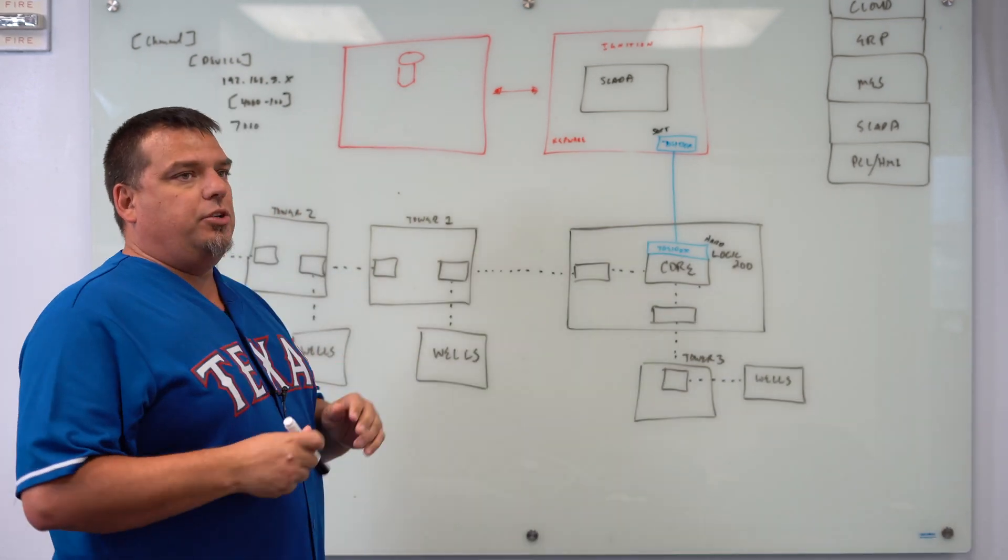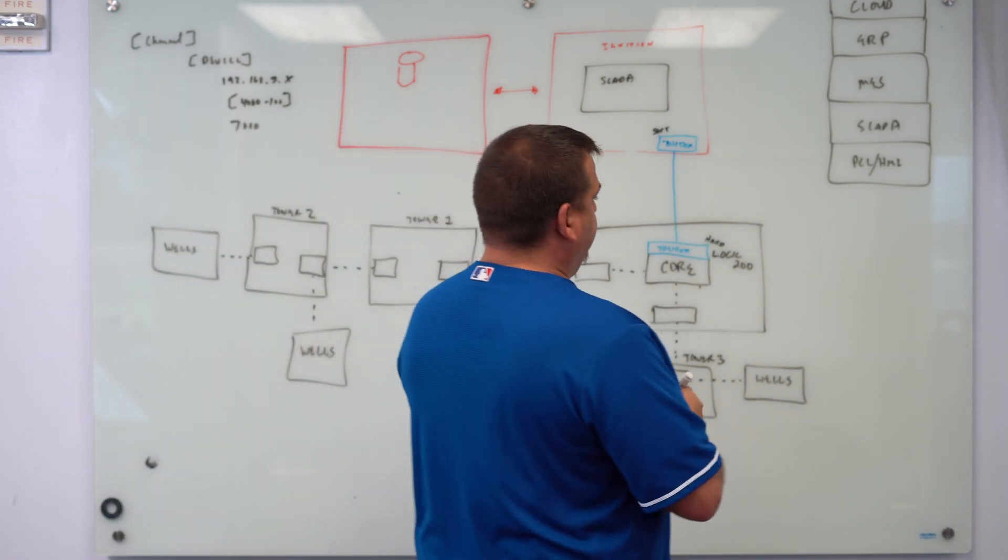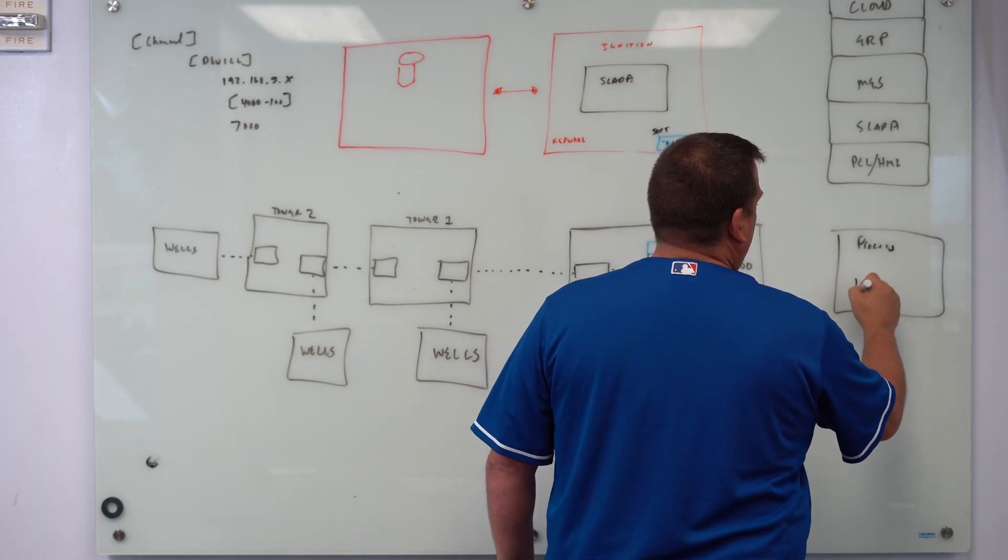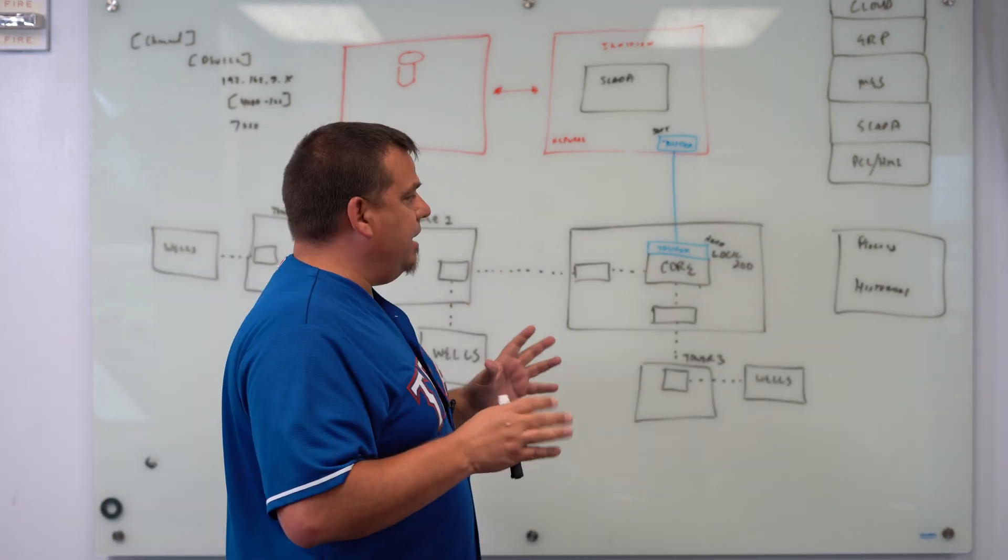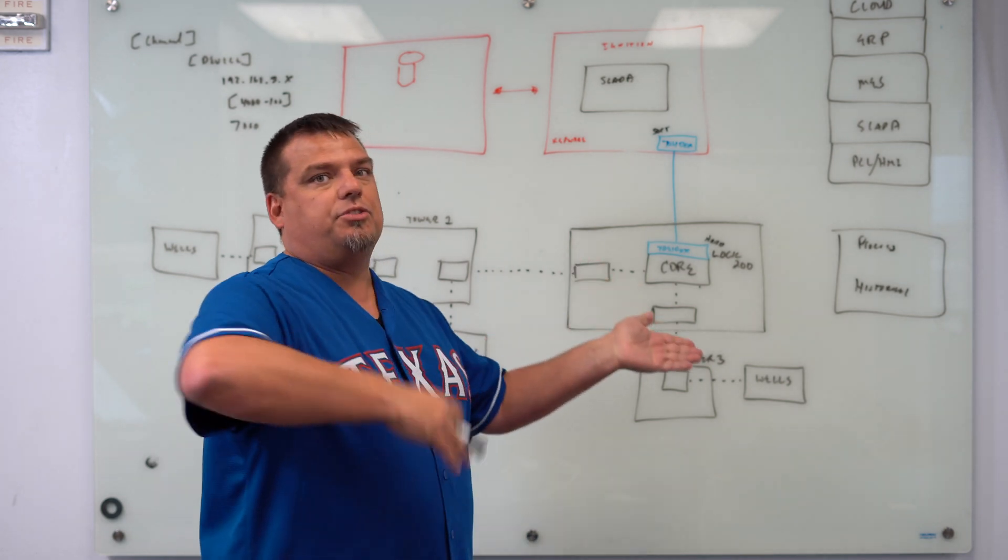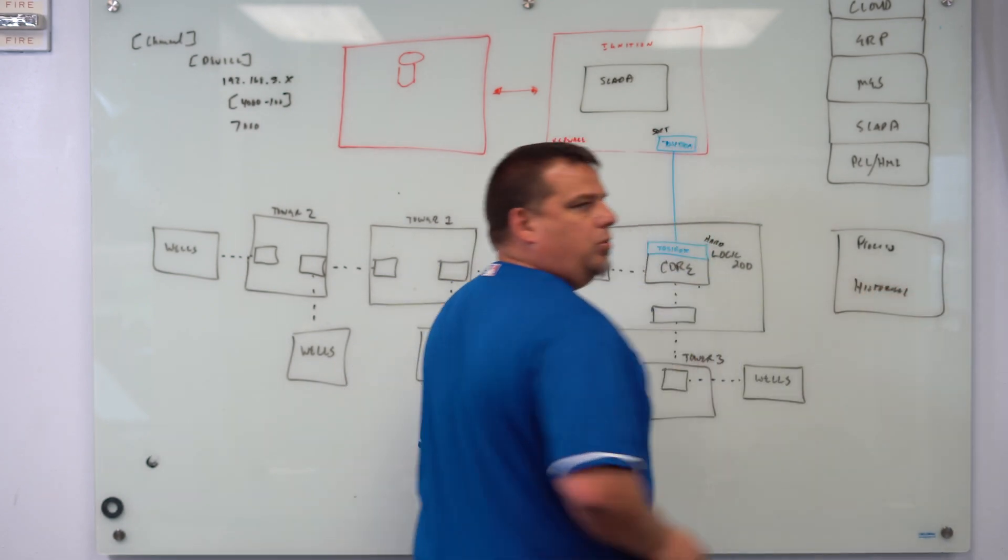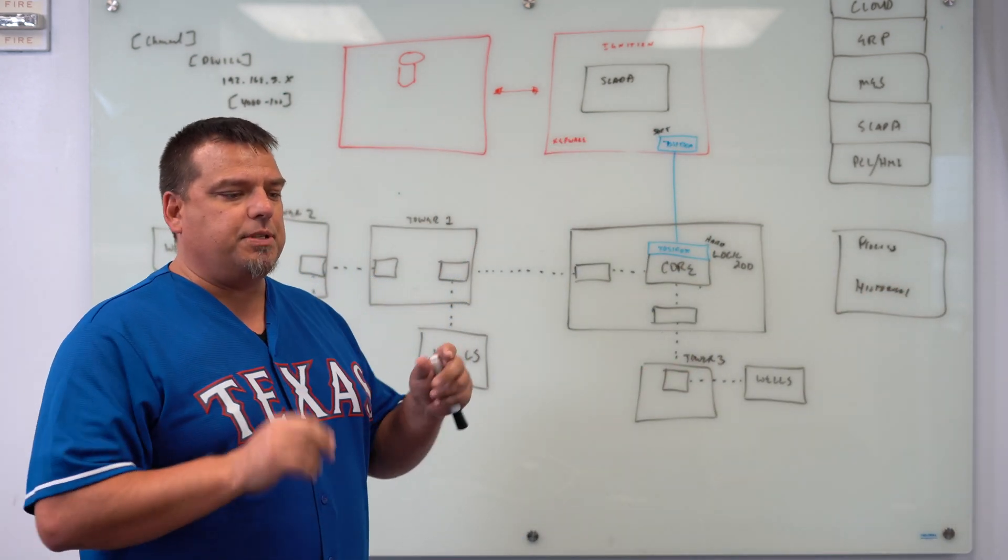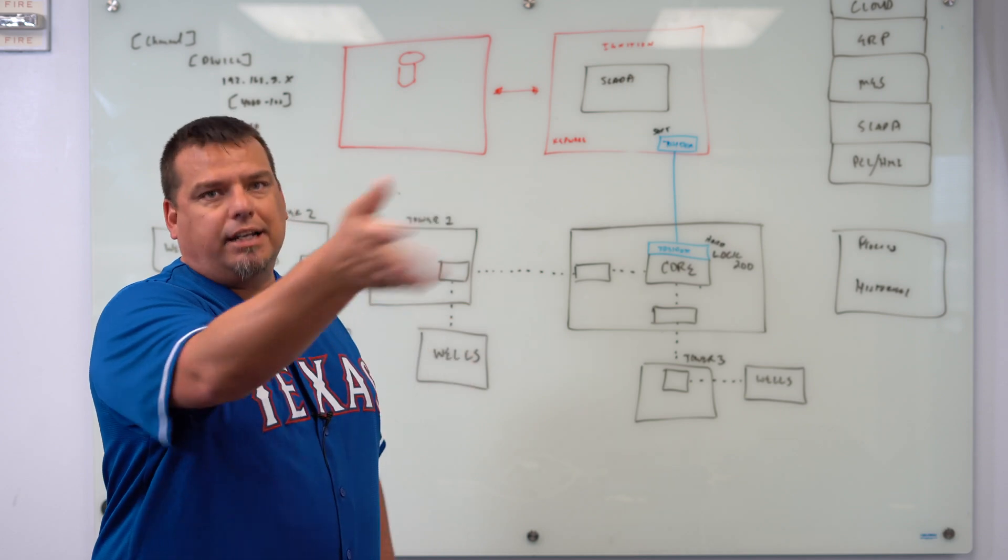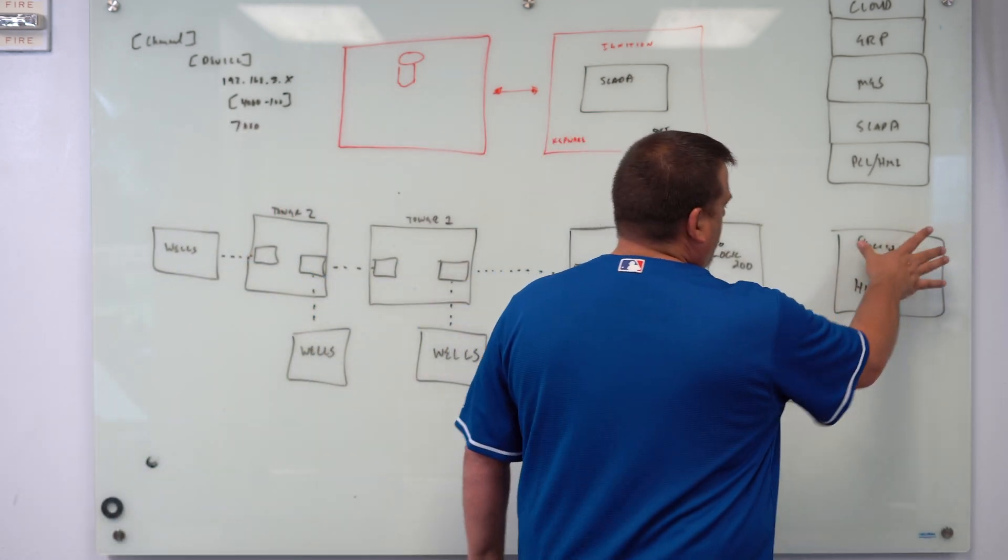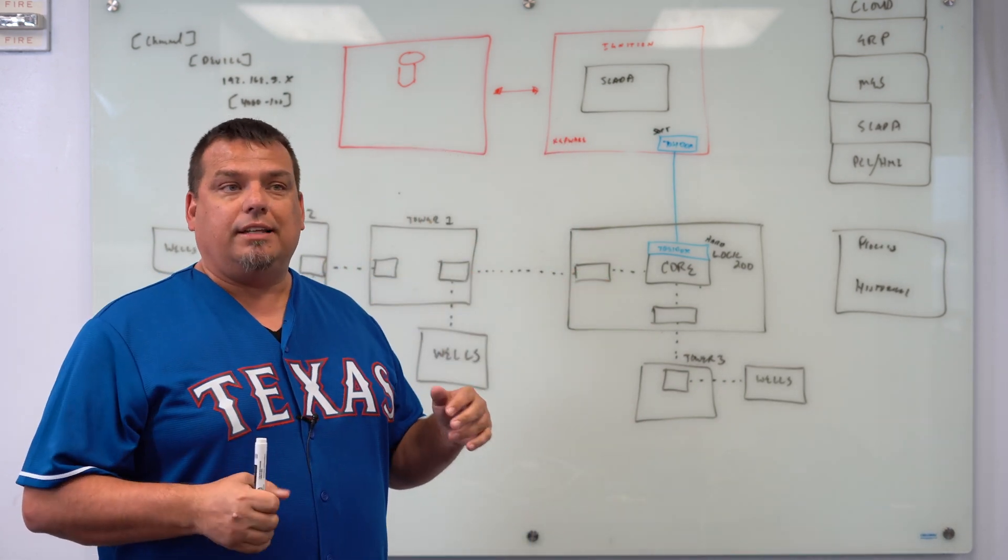We've configured Kepware to talk to all 550 devices. Because we are using the EFM exporter - so in an ABB total flow, in the total flow we've got here, you have process control and then you also have historical data. Inside of an EFM, essentially these are all gas lift wells. Inside the ABB total flow - these are all G3 and G4s, generation 3, generation 4 EFMs - you have process control. In this case, they're using the plunger lift program. They're able to make adjustments to how much pressure we want the well to be under before we open up the valve and allow the fluid to come out and go into the tank. It's pretty simple process control. There's process control in there and then there's historical data. All of the alarms - there are alarms on the edge that will shut that well in.